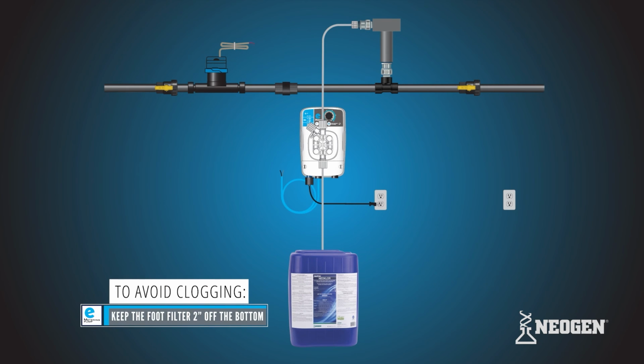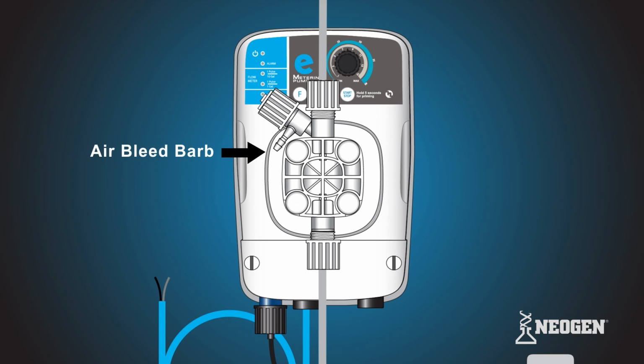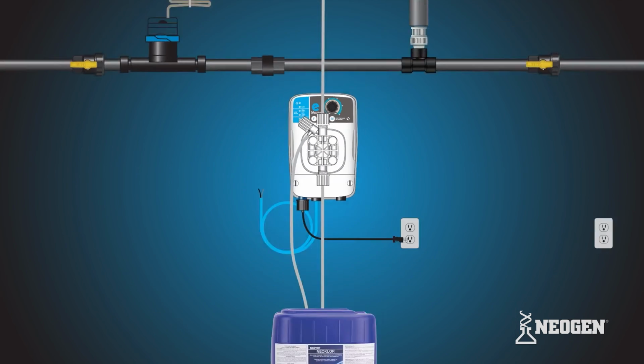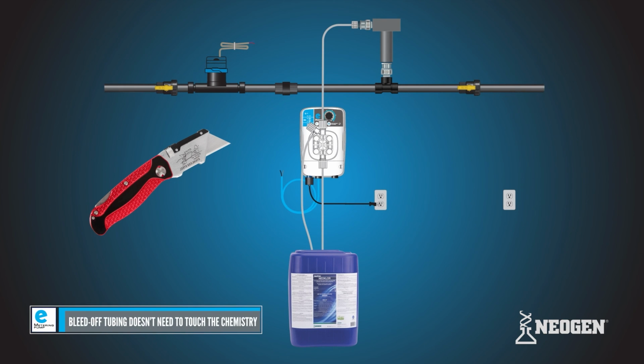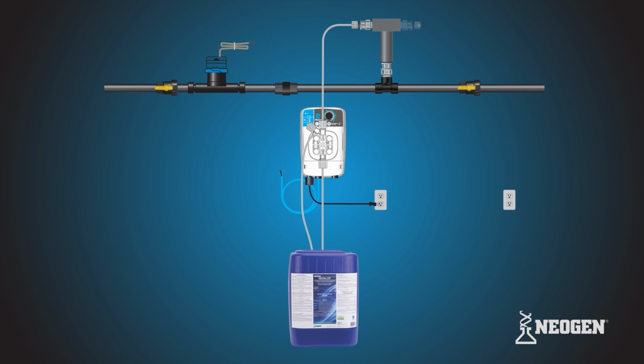Take the remainder of the clear, flexible PVC tubing and locate the air bleed barb on the upper left section of the pump head. Slide one end of the PVC tubing over the barb. Using the cutters, cut the tube so the tube is long enough for the chemical bleed-off to go back into the bucket or stock tank while priming. Repeat these instructions to install your second pump.